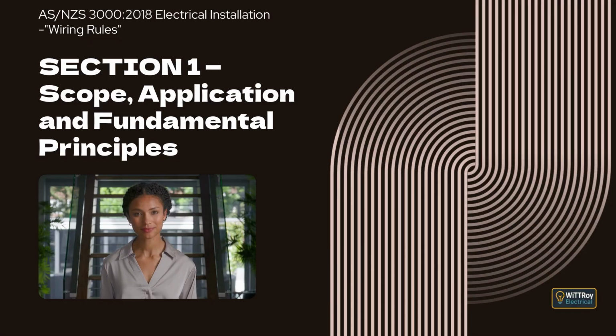Clause 1.5.5.1, General. This clause explains the purpose. Whenever there is a chance that exposed metal might become live because of a fault, we must have protection. The method we choose depends on the environment and the equipment, but the goal is always the same: prevent electric shock under fault conditions.